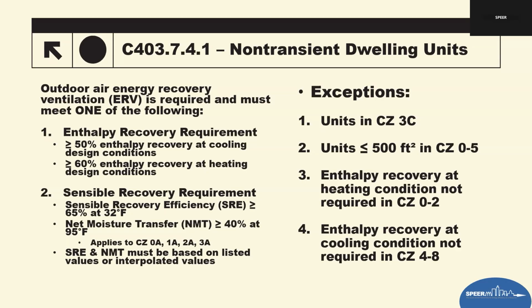The SRE is greater than or equal to 65% at 32 degrees. And for humid climates, such as what most of Texas is under, you've got the net moisture transfer of greater than or equal to 40% at 95 degrees. So the SRE covers basically heat transfer only, while the NMT reflects the ERV's ability to transfer moisture. There are climate-based exceptions. In climate zone 3C, the ERV is not required. Units under 500 square feet in climate zones 0 through 5, basically very small units in these zones, are exempt. Heating conditions, basically these zones rarely experience significant heating loads, or when you've got cooling in climate zones 4 through 8, these zones also experience less cooling, so that's in the colder climates.